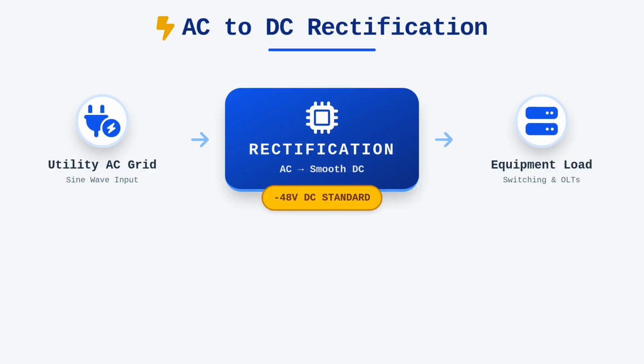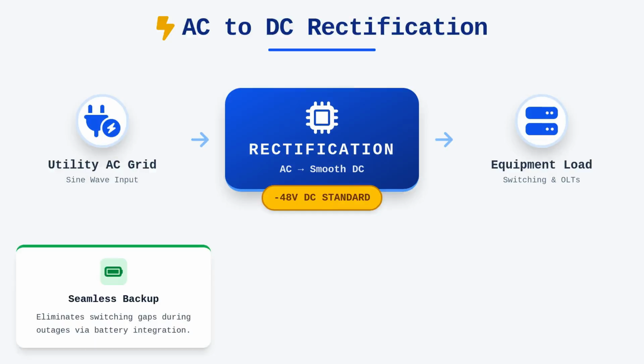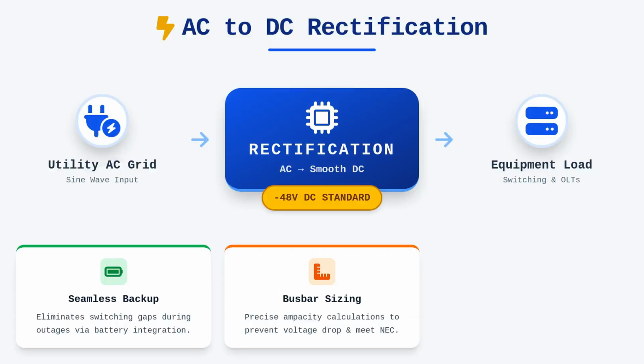The conversion from AC grid power to DC is handled by rectifiers, which translate the utility's sine wave into a smooth, steady, unidirectional current. As a designer, you are responsible for calculating the total ampacity requirements to ensure that copper bus bars are sized correctly to prevent excessive voltage drop and thermal buildup. Sizing these bus bars is not merely about current carrying capacity, but also about managing the physical dimensions of the conductor to maintain efficiency and meet NEC clearance requirements.